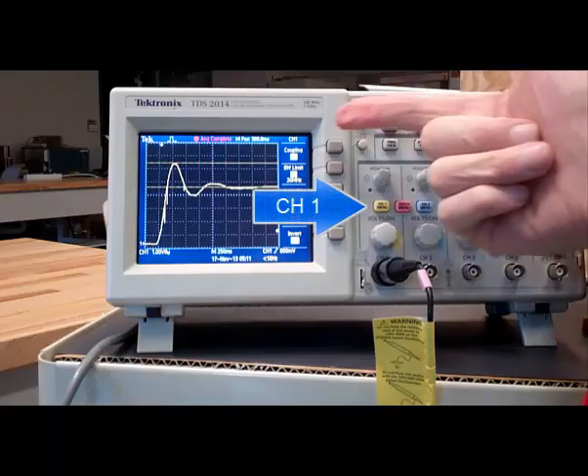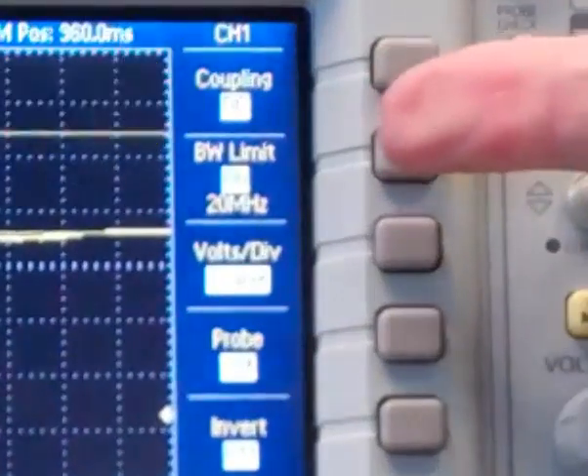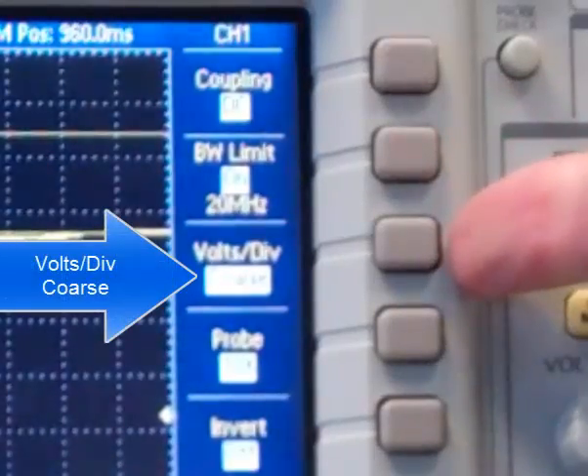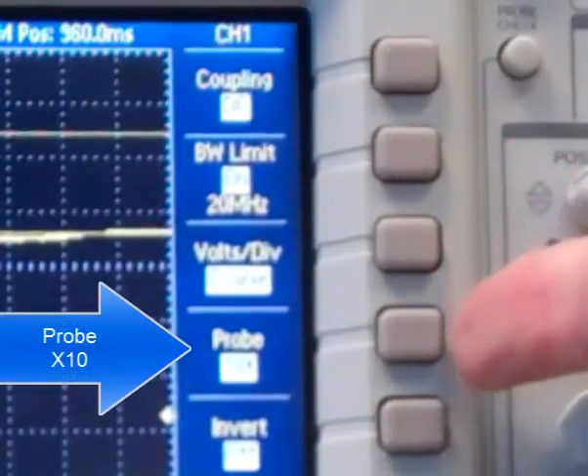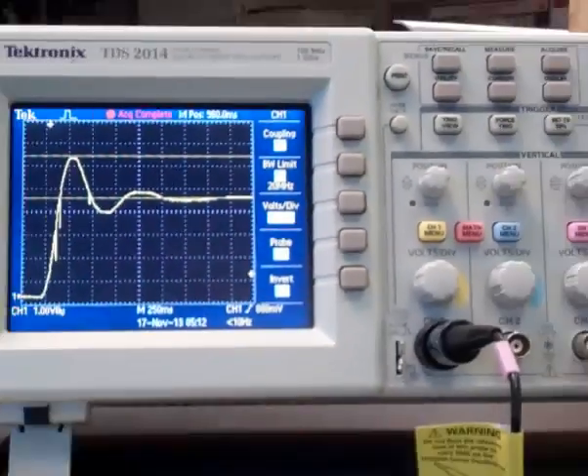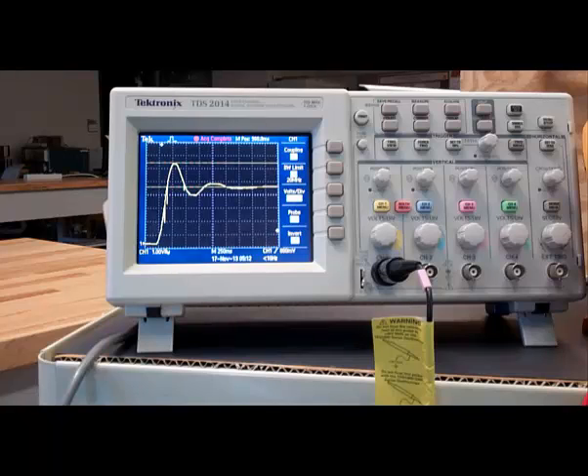Channel 1 should be on DC coupling, bandwidth limit on, coarse volts per division, probes times 10. Make sure the probe is set for times 10. And then the oscilloscope should be ready to capture this signal. That's all.